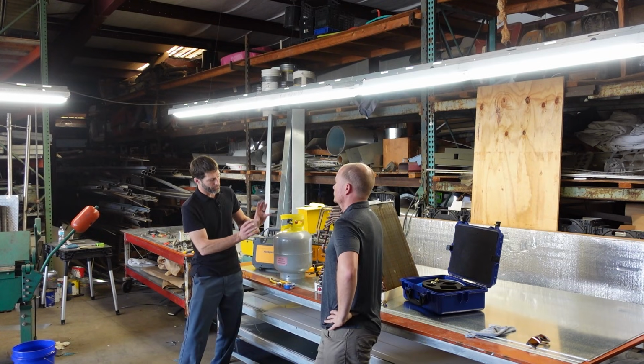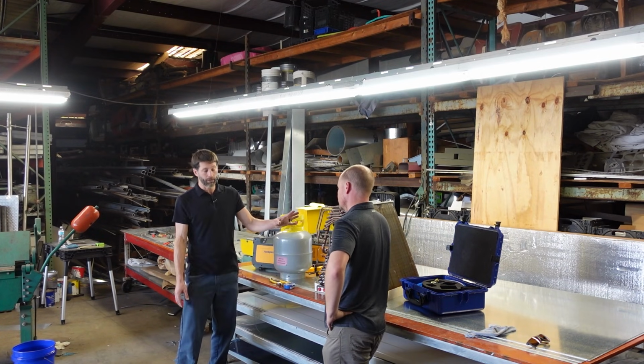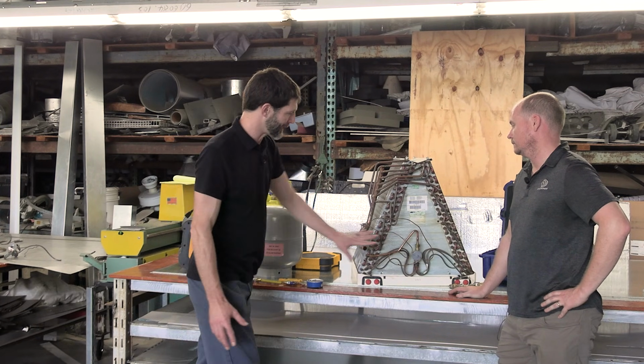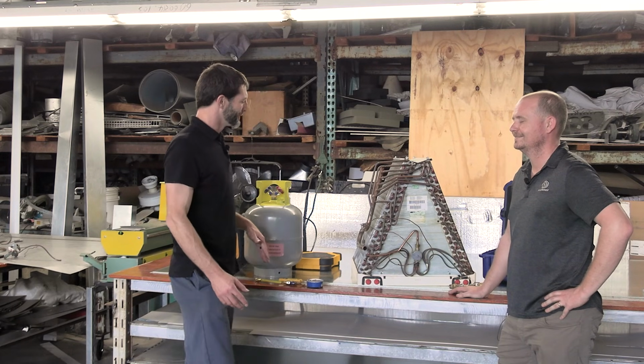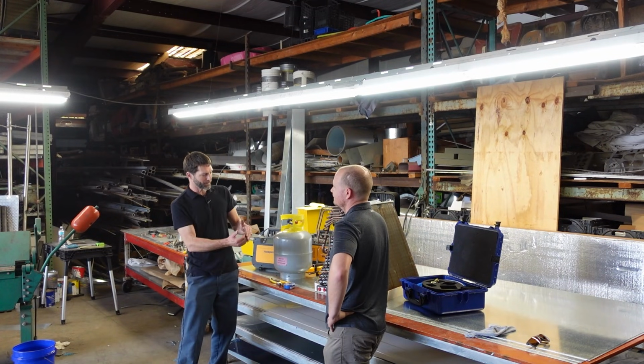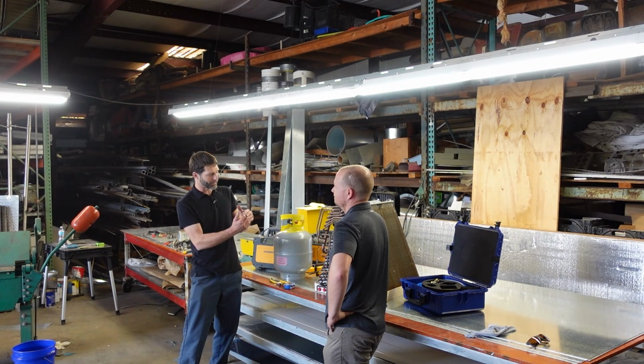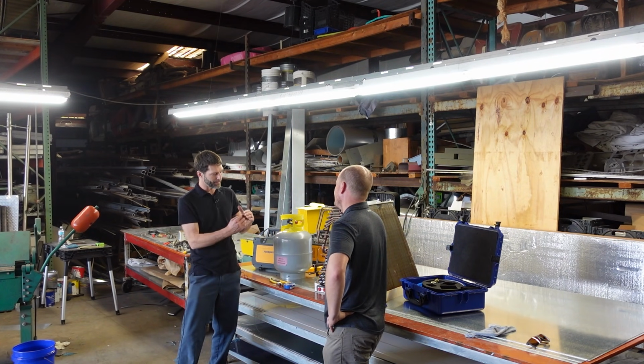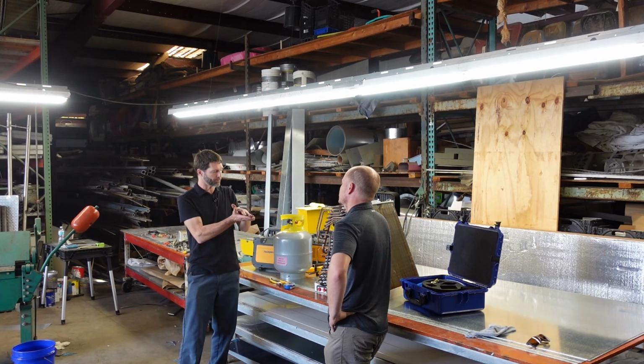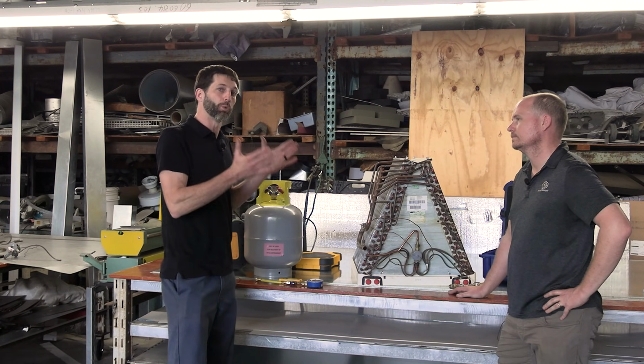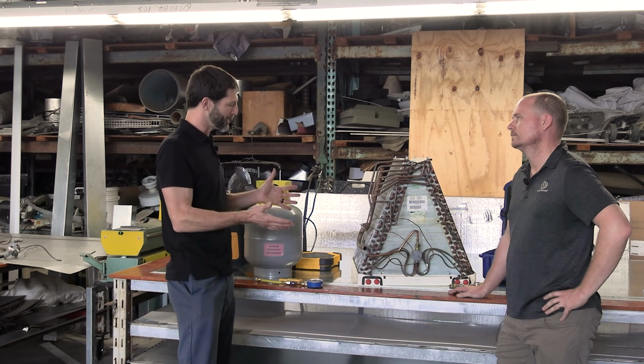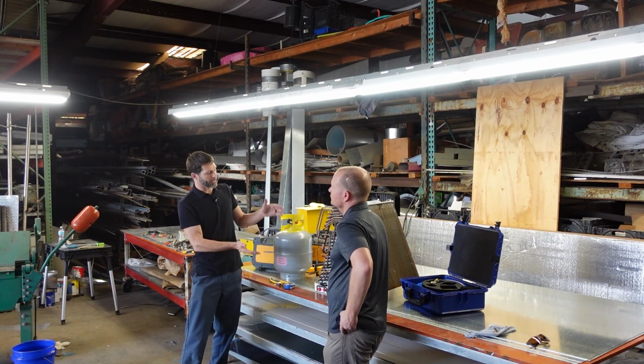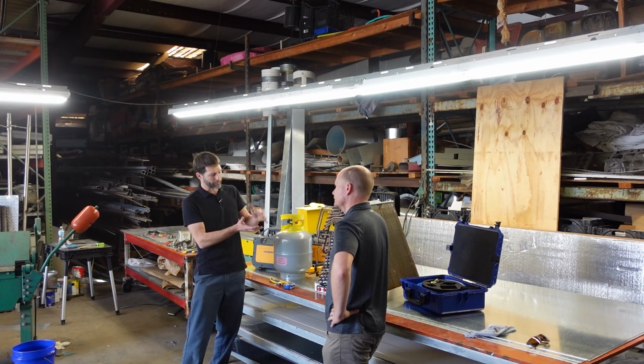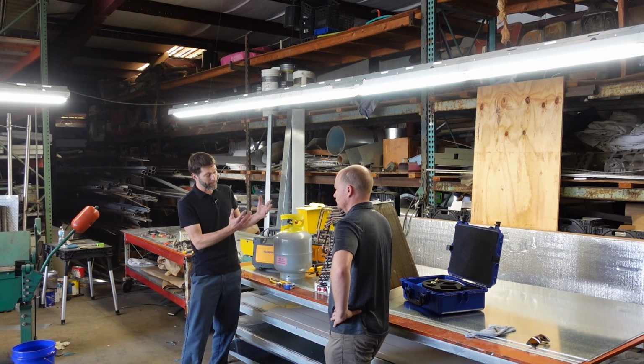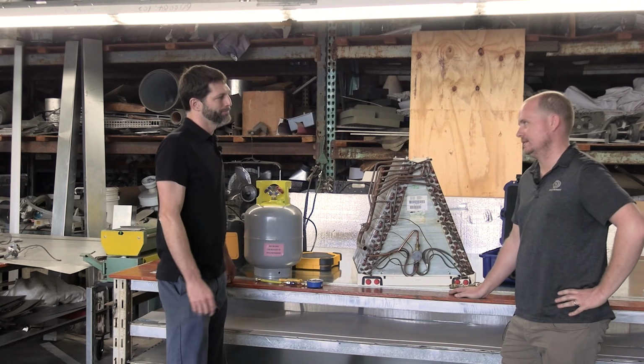But once again, I advocate that you put some type of heat on the system, and a good place to do that is at this big heat exchanger here, so that once you get it down below 0 psig and the whole system is shut off, it rises, but it doesn't go above 0 psig. That will be great if you can do all that in one shot. The problem is when it rises and you have to go back and try to recover the rest of the refrigerant that has vaporized. Yeah, you want to make sure that it stabilizes. That's the big thing.